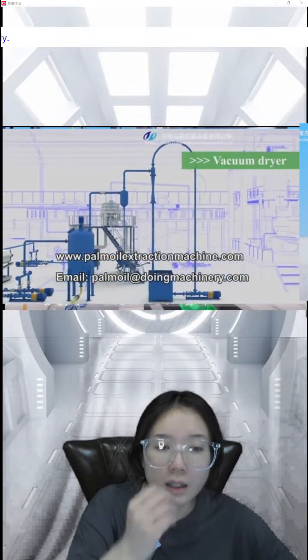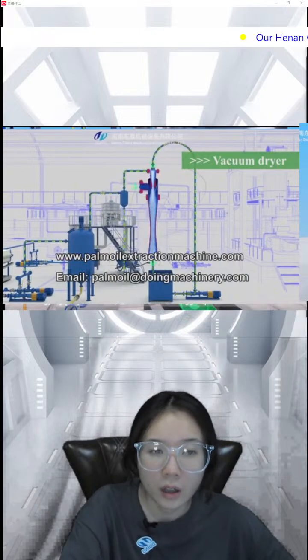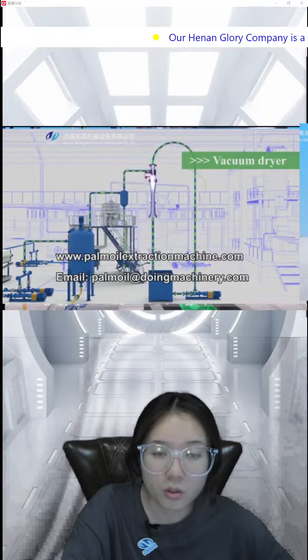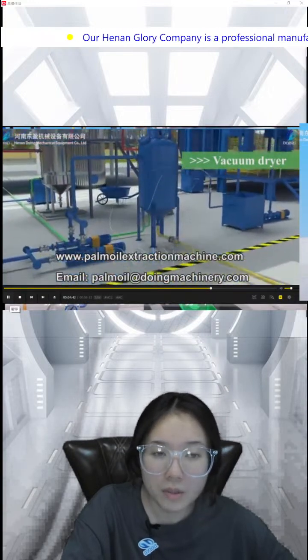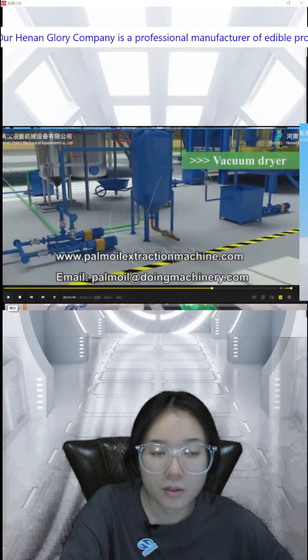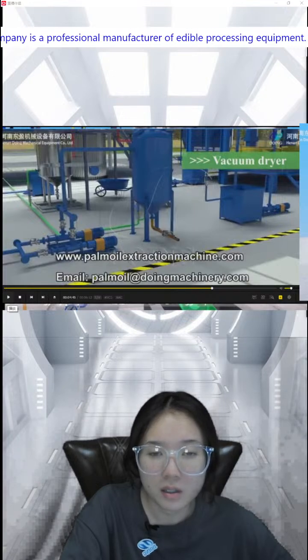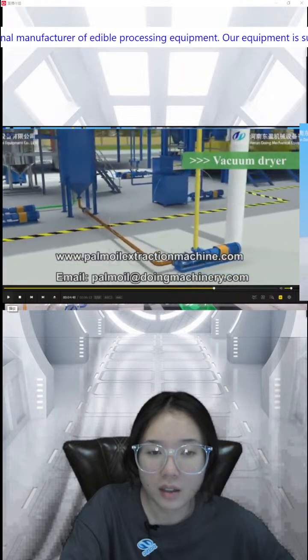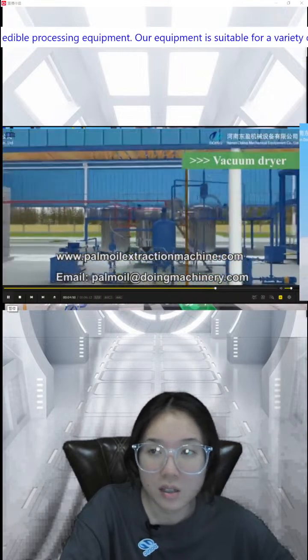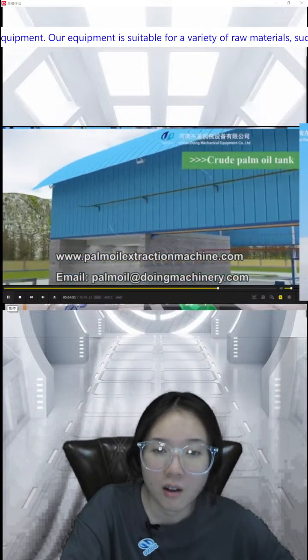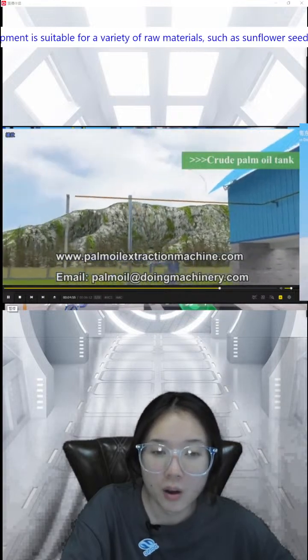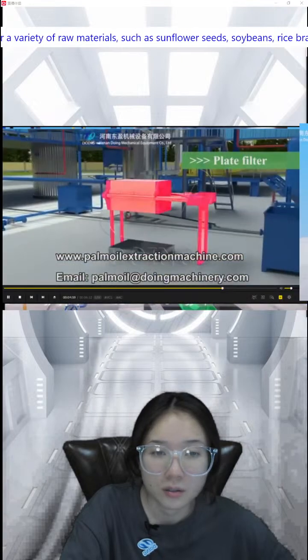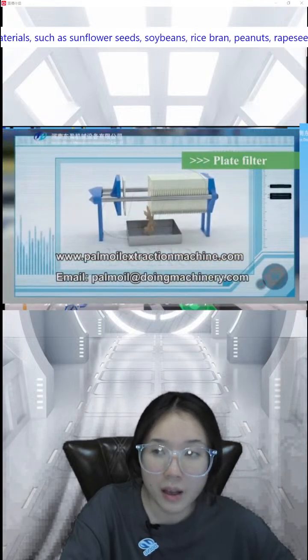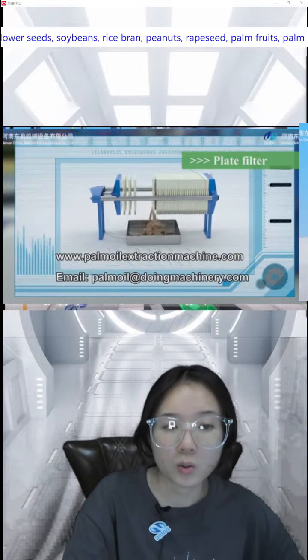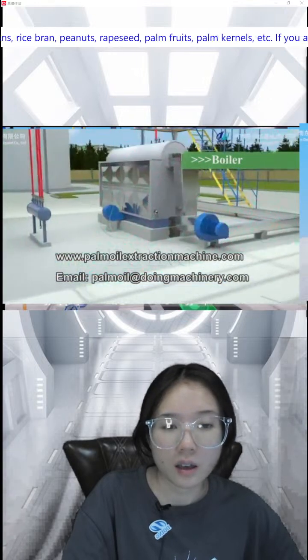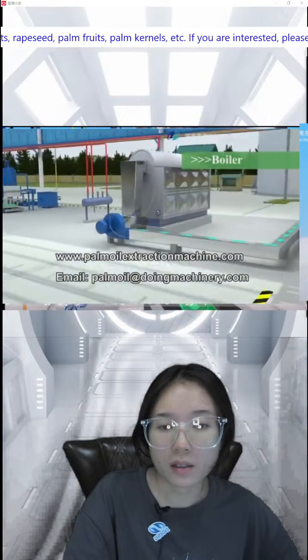Our vacuum drying tank also has a steam coil to provide a heating environment for the oil. When the oil temperature reaches about 85 degrees under a vacuum environment, the water will evaporate and reduce our steam usage. The back half is the water jet vacuum pump, which provides a vacuum environment for the vacuum drying system. By converting the potential energy into kinetic energy, the air inside the tank is pumped away to realize the effect of vacuuming.